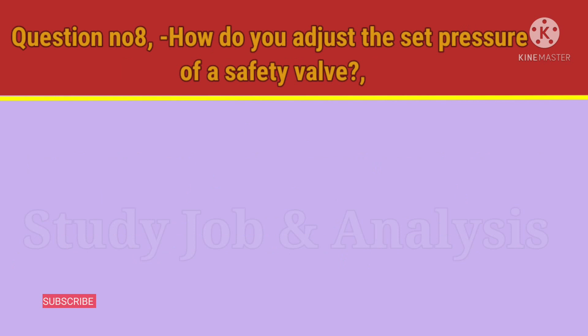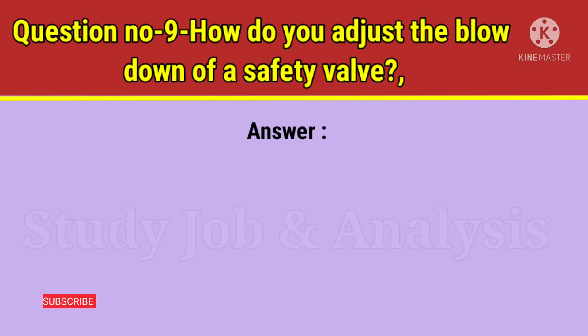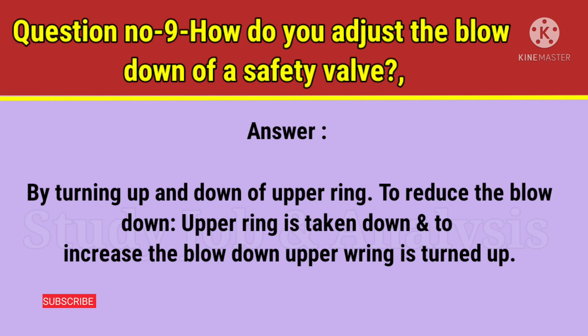Question number 8: How do you adjust the set pressure of a safety valve? Answer: The safety valve is set by adjusting the compression of the spring. Question number 9: How do you adjust the blowdown of a safety valve? Answer: By turning up and down of the upper ring. To reduce the blowdown, the upper ring is taken down; and to increase the blowdown, the upper ring is turned up.